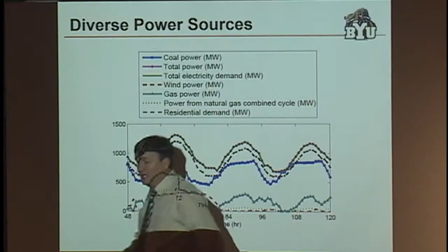So in this case, we were able to avoid a bunch of very costly things. The utility company actually pays people to have power generating systems on standby, called spinning reserves. Mona is an example of that — if you drive down the highway, that's one of the spinning reserve locations that Pacific Corp has for generating power. They have things just spinning and ready to generate power on a moment's notice, but they might not actually generate power for weeks or months, because demand doesn't get high enough. But you still have to build them and keep them spinning, ready to go, and that's extremely costly power.